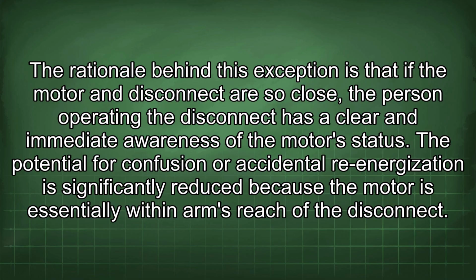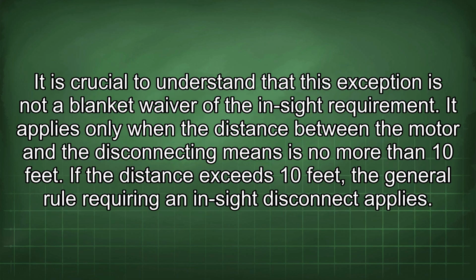The potential for confusion or accidental re-energization is significantly reduced because the motor is essentially within arm's reach of the disconnect. It is crucial to understand that this exception is not a blanket waiver of the in-sight requirement. It applies only when the distance between the motor and the disconnecting means is no more than 10 feet. If the distance exceeds 10 feet, the general rule requiring an in-sight disconnect applies.